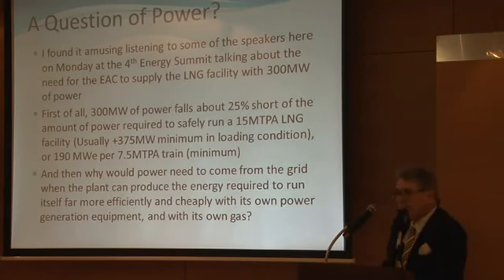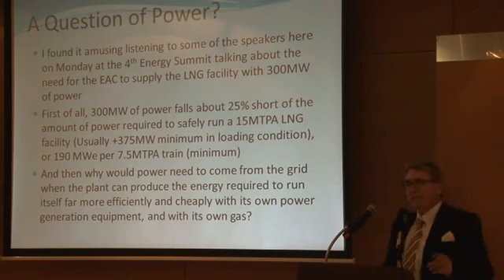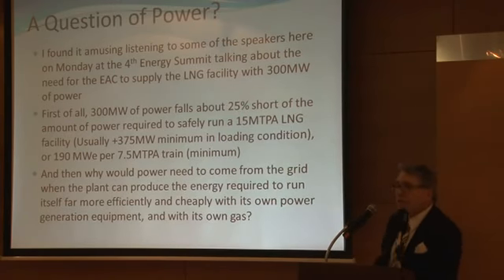I should have drawn an overview of a process train, because from the air, an LNG process train is just a mass of radiators. We use 10-metre diameter rotors to directly or indirectly cool tubes - it's just one massive heat exchanger. For a 7.5 million tonne per annum train, your bank of fin fans alone is 8 wide by 330 metres long, with 10-metre diameter fans. You've got to power all those motors - that's why you need a huge amount of power.